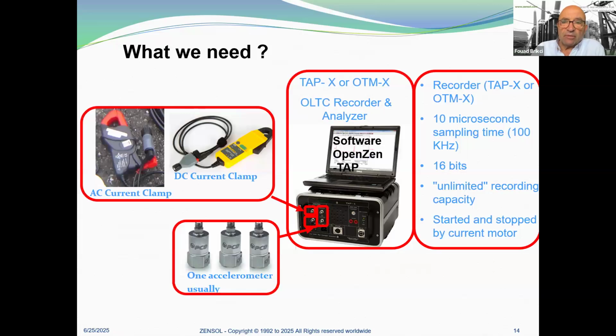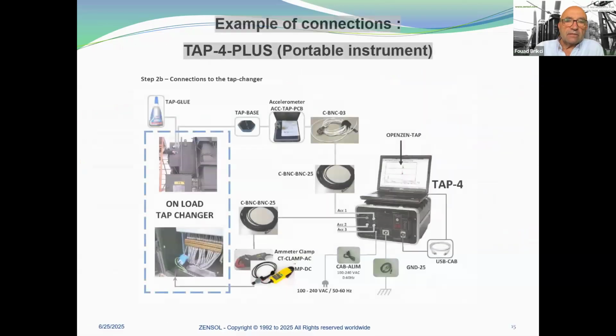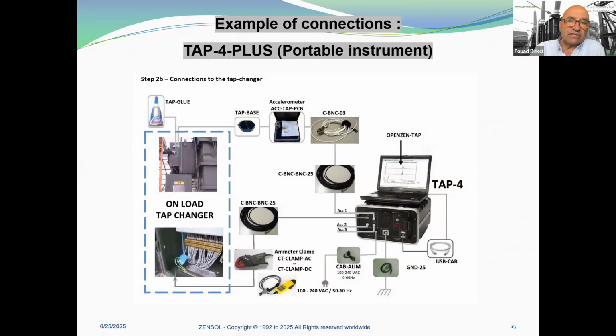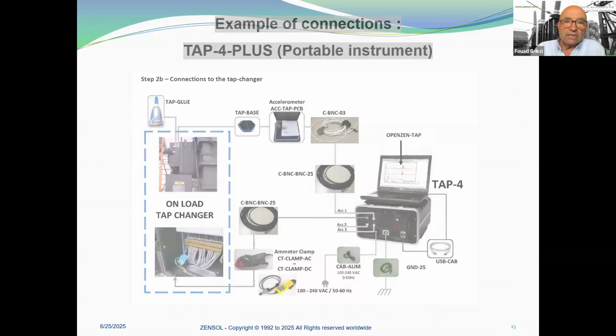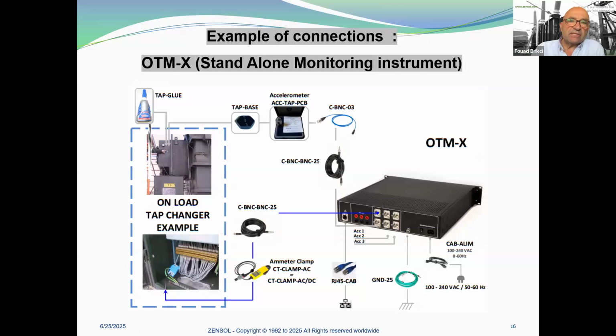So what do we need? In order to apply the vibroacoustic, the user will need the following equipment: a current transducer, AC or DC, the tap changer analyzer, a computer with OpenZen Tap, and at least one accelerometer per phase with the related mounting base. The characteristics we will see on the next slides. Here is an example of connections of Tap 4 Plus, which is the portable instrument. Here you can see the glue, where we install what we call the tap base, where we screw the accelerometer, and it comes here. Then the AC current or DC current. We do exactly the same connections for an OTMX, which is our standalone monitoring system instrument.